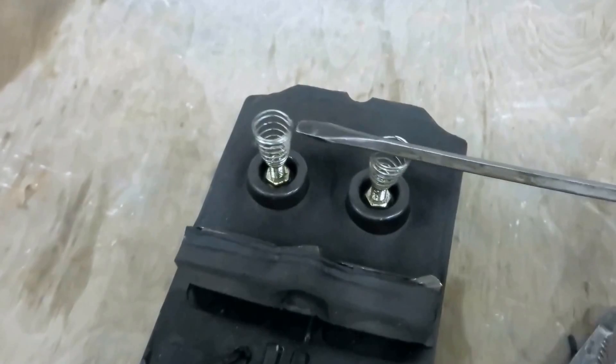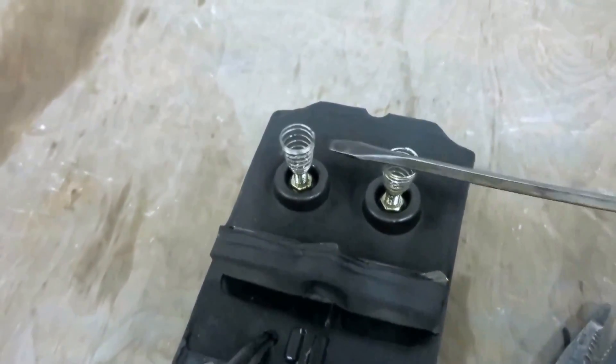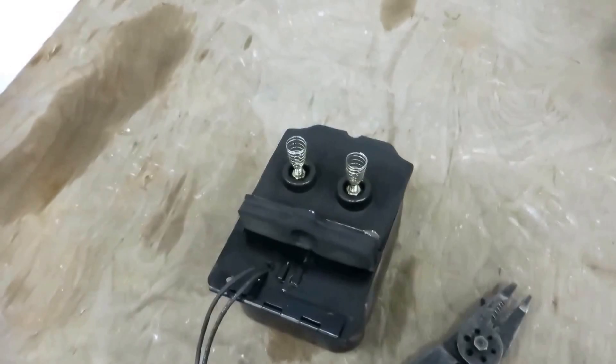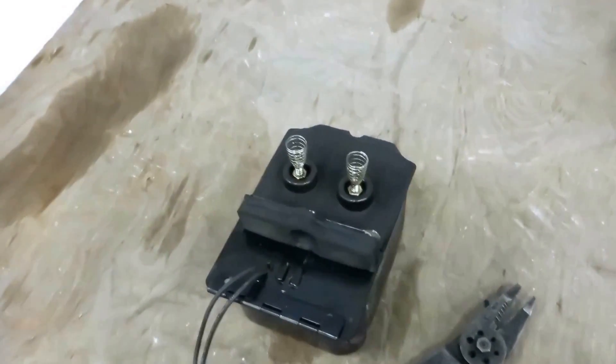So that transformer I took off a job—I know it's junk. Obviously this burner wouldn't start because it's not getting any spark, and the thing will trip out on safety.